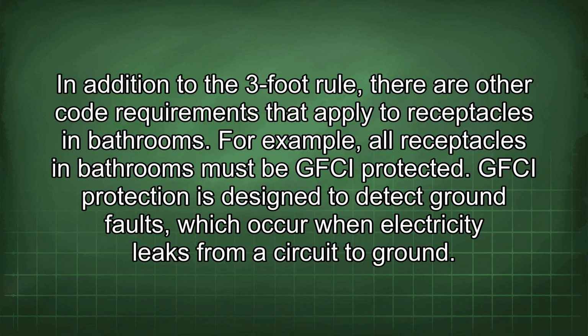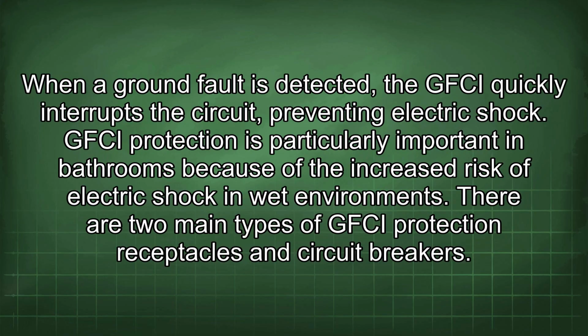In addition to the 3-foot rule, there are other code requirements that apply to receptacles in bathrooms. For example, all receptacles in bathrooms must be GFCI protected. GFCI protection is designed to detect ground faults, which occur when electricity leaks from a circuit to ground. When a ground fault is detected, the GFCI quickly interrupts the circuit, preventing electric shock. GFCI protection is particularly important in bathrooms because of the increased risk of electric shock in wet environments.